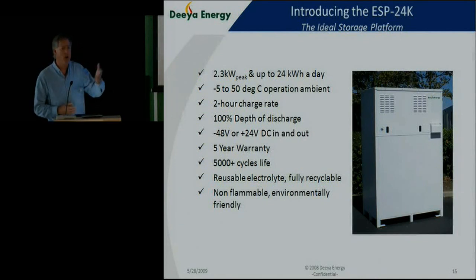So for example, if you had a UPS based system and you had a 4-hour outage, the battery can cover that outage very easily, and then would only take 2 hours to recharge itself to get the system back to a place where it's 100% ready for the next outage. Of course, you can discharge the battery completely to zero, with no energy storage at all, and it has no ill effect on the battery whatsoever. So again, that's a very high value feature. Because of the reliability of the system, we offer a 5-year warranty.